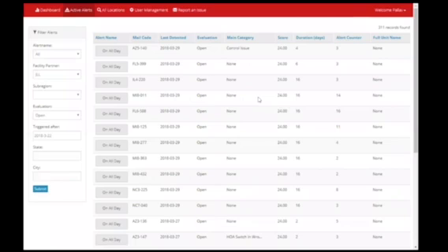So one of the first things they do early in the year, starting about February to April as spring is starting, is focus on heating and cooling issues. They ensure all the worst heating and cooling issues are resolved, using a combination of things. They look at the alert counter, and if it is going up over and over, to them that indicates an equipment problem and equipment that is a good candidate for replacement.